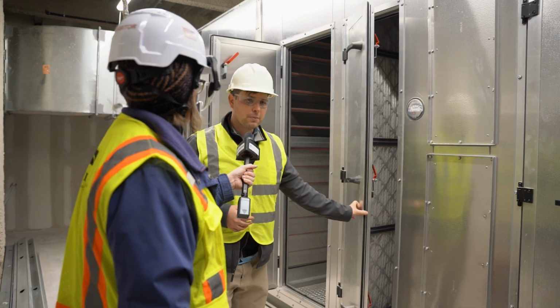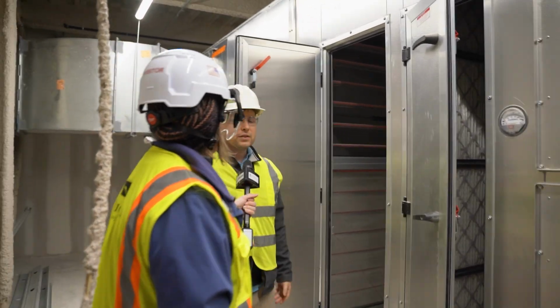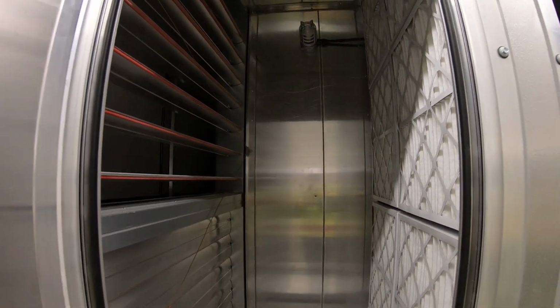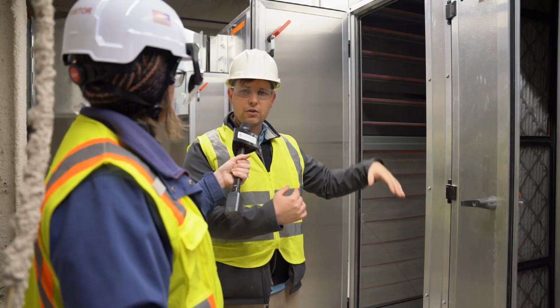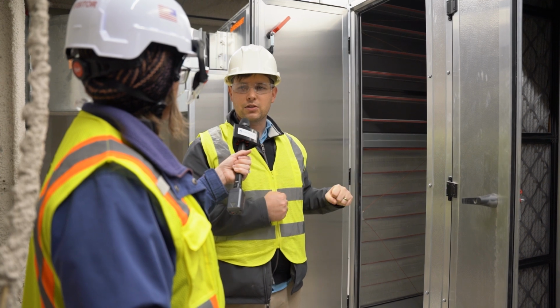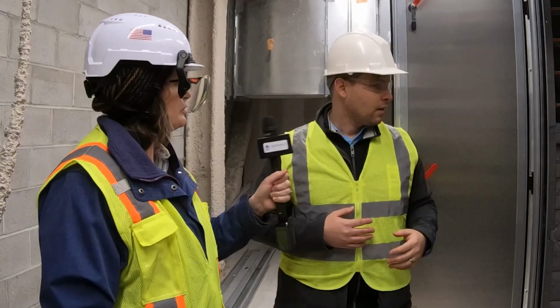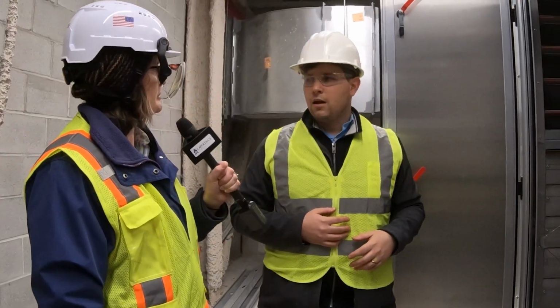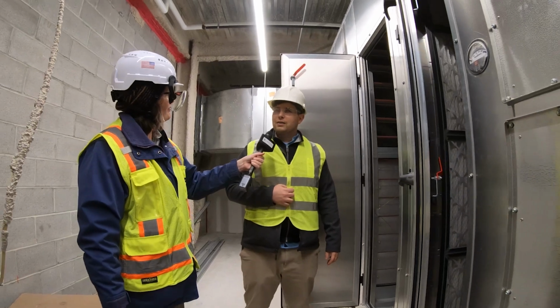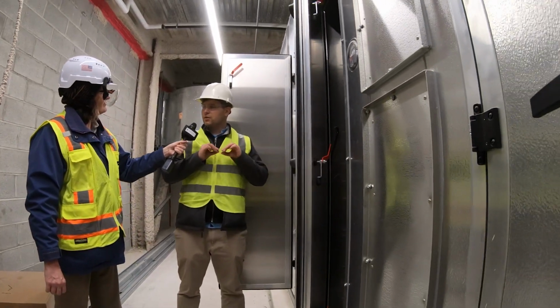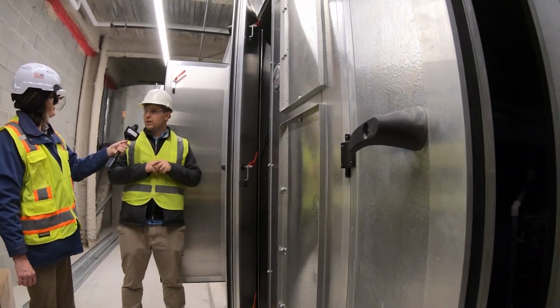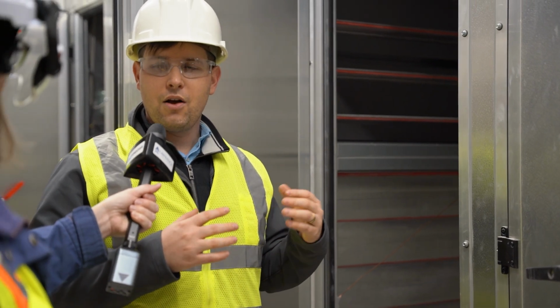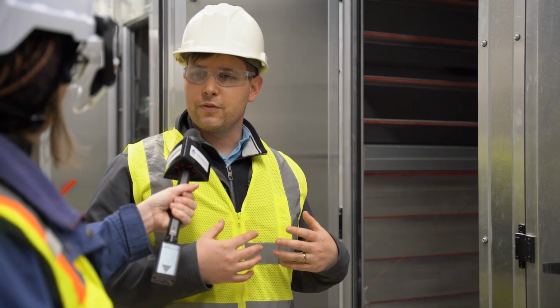Next is the energy recovery, which is a rather interesting form. It's a block—air comes through one side and pushes through the other, switching sides so it can recover more energy. The block is aluminum with a very good heat transfer coefficient, and it also has a desiccant coating, a fancy way of saying the all-metal core can harvest humidity from the air as well.